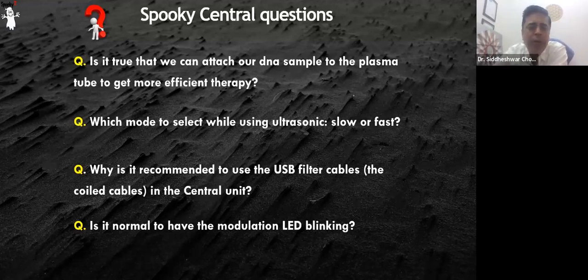Why is it recommended to use the USB filter cables in the central unit? USB filter cables are used to send back the oscillations received from the central unit. It protects the Generator X from the oscillations generated by the central unit. So the protection is needed. Otherwise, your generator will get locked up easily. So you must use the filter cables if you want to avoid these issues.